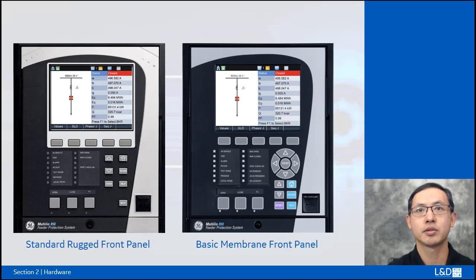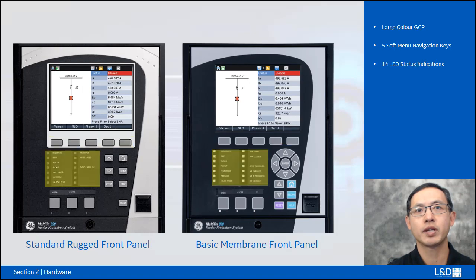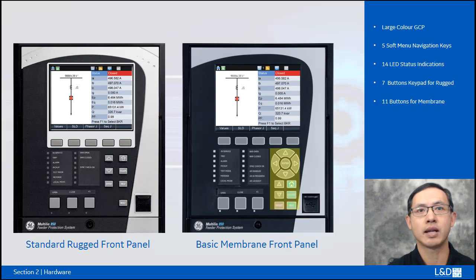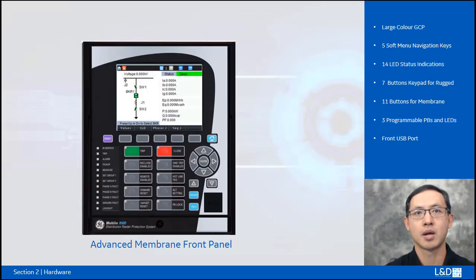In the front panel of the rugged and membrane type relay, there is 1 large color graphic display GCP used to view the device and system status, alarms and event logs, single line diagram, and metering information. 5 soft menu navigation keys used to enter the menu corresponding to the labels on the tab. 14 LED status indication, 7 push button keypad for the rugged, and 11 push button for the membrane, and 3 programmable push buttons and LEDs, and 1 front USB port. For the advanced membrane panel, instead of 3 programmable push buttons, it has 10 push buttons and LEDs.